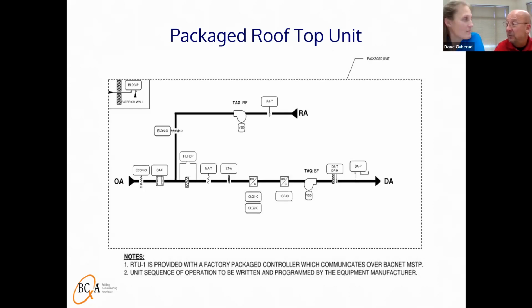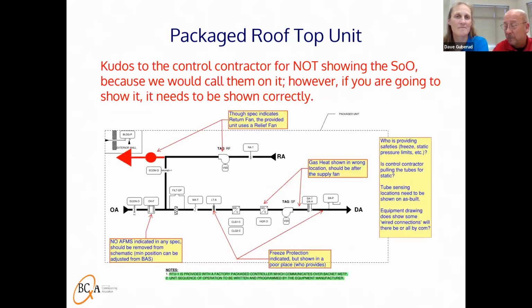And before we flip to the next screen, to accentuate where Rachel just went, the engineers oftentimes might write a pretty robust sequence of operation for a pretty cheesy rooftop unit. If everyone's going to be writing that information, including the control contractor, then when we come to functional testing, if we're not told otherwise, we're going to really hold the control contractor to, this is how you said you were going to make it work. So this is why we were happy that they didn't show that, because it allowed for a better conversation during the page turn, since we had the vendor and the control contractor there, so they all worked it out. But now to our next picture pertaining to this: if people are going to show a schematic, they should really show it accurately.